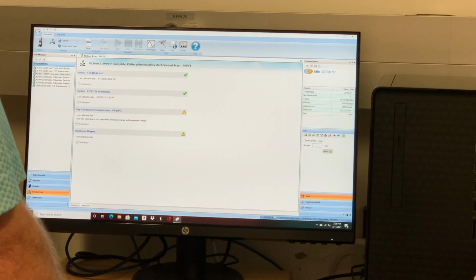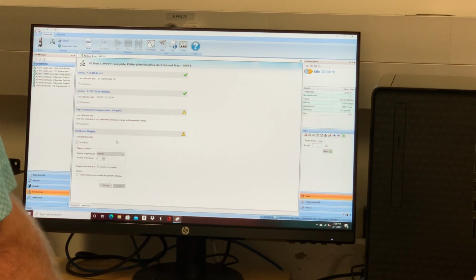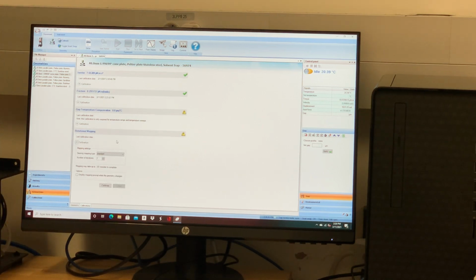And then the last calibration here is rotational mapping. What rotational mapping does is map the encoder, the thing on top. It's mapping out those small little torque variations that I was telling you about earlier. Every bearing has tiny microscopic imperfections that cause torque variations, and that's what it's mapping out. Okay?